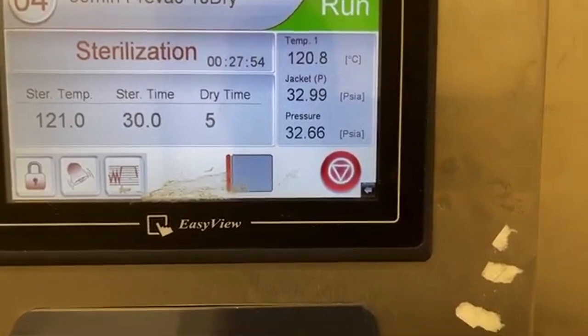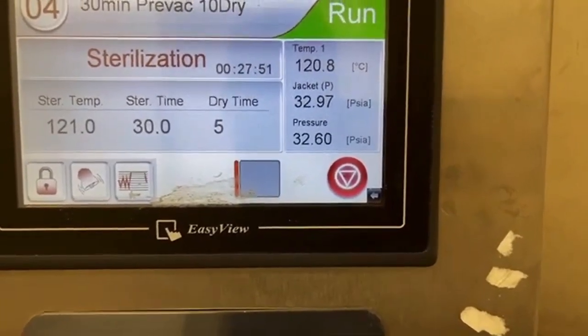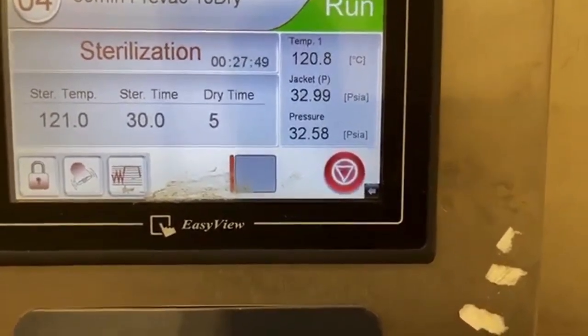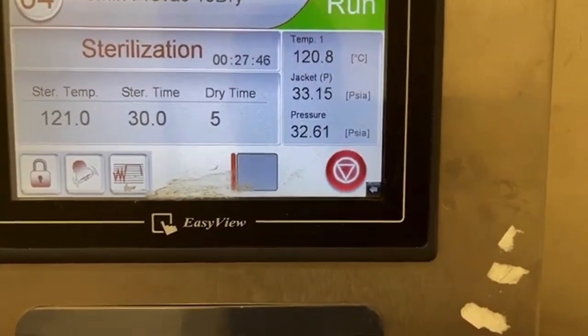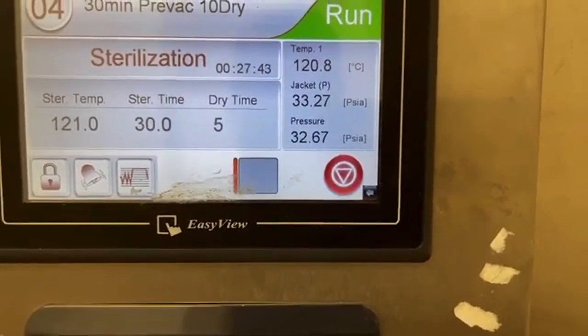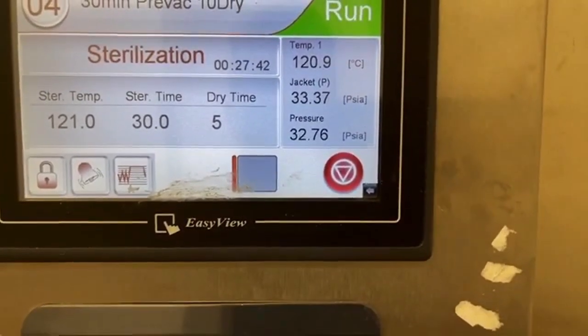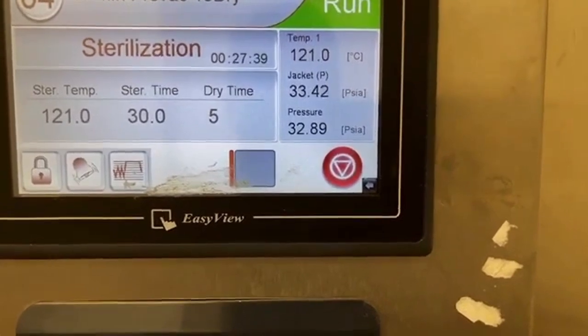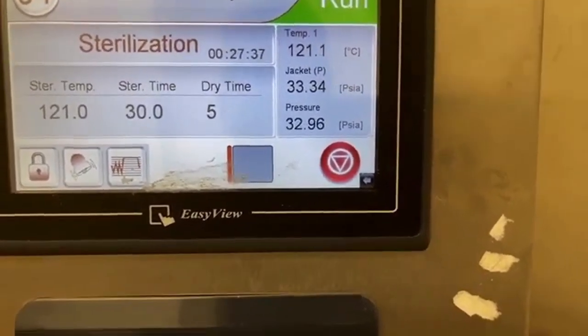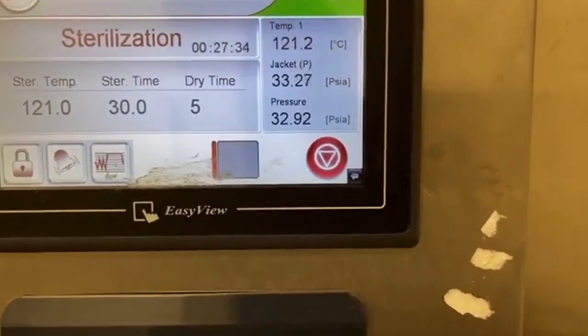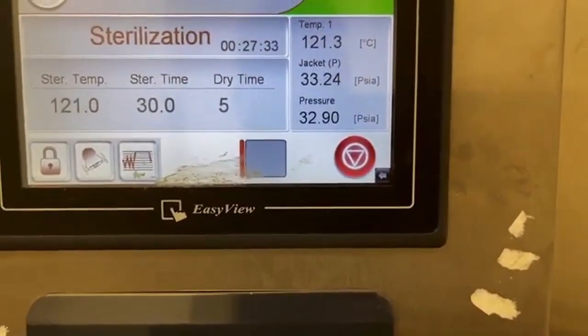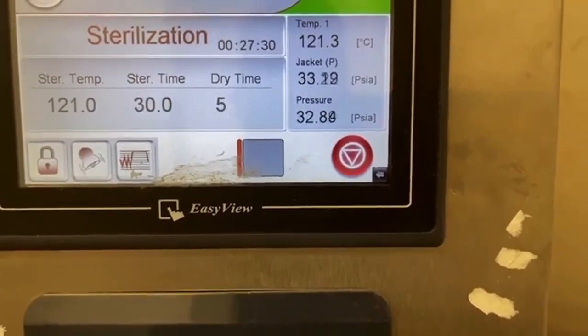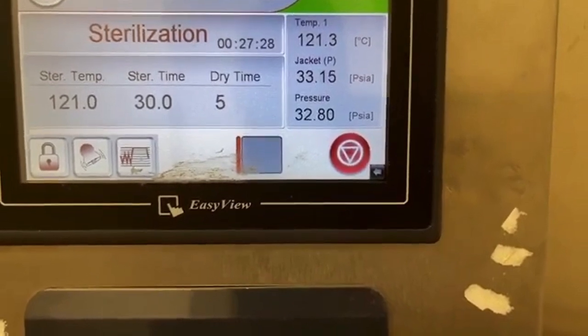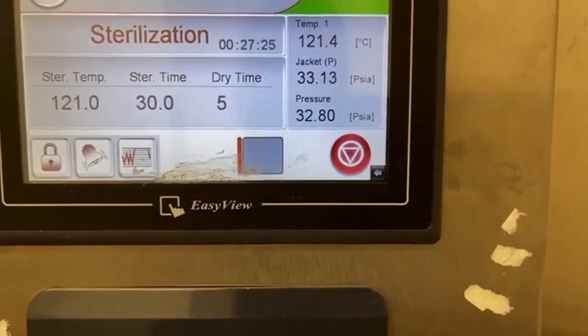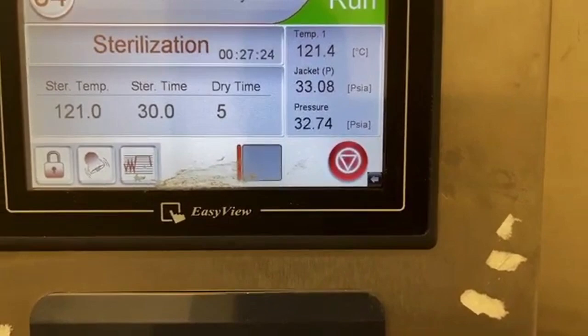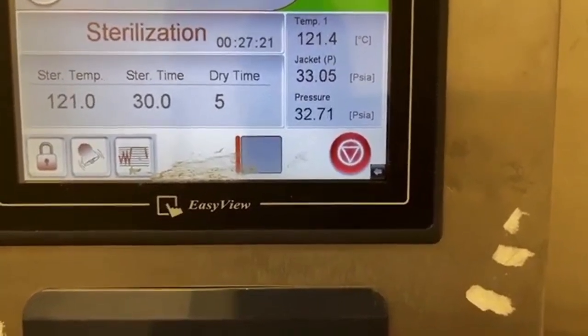There. We're just a little over 2 minutes in. The last run, it actually achieved sterilization for the middle of the load when it kicked over. This was the biggest piece of meat I could find, and there you have it. So 2.5 minutes later, we have 27:30, we'll call it 27:30 left on the sterilization cycle, which is more than adequate to give us a good BI and a good kill on anything that's in there.